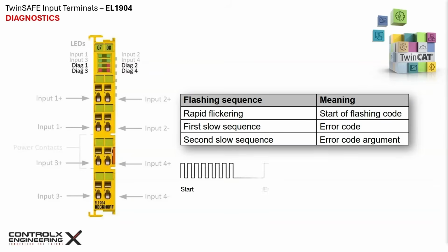The diagnostic 4 LED indication starts with rapid flickering followed by a first slow sequence indicating the error code and then a second slow sequence indicating the error code argument, as shown here. The flashing code is repeated after the second slow sequence, which is again followed by rapid flickering. The full list of error codes can be found in the product manual.